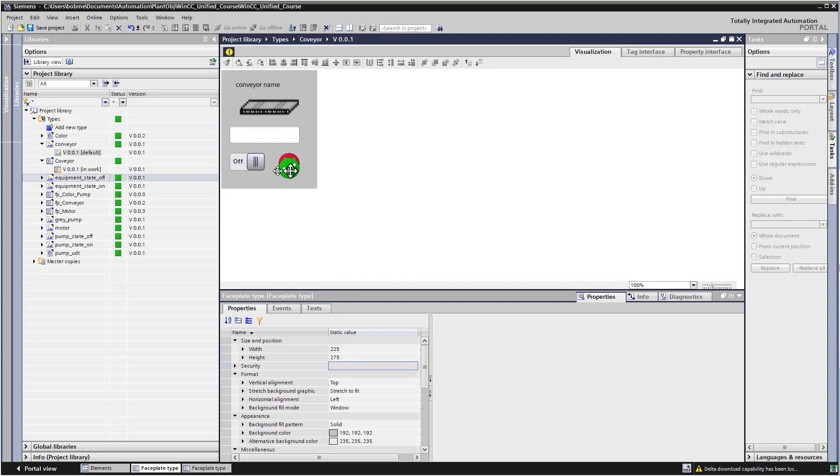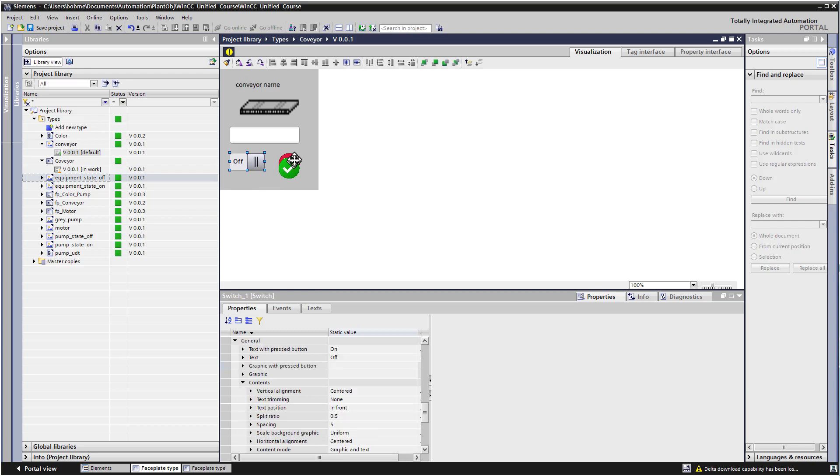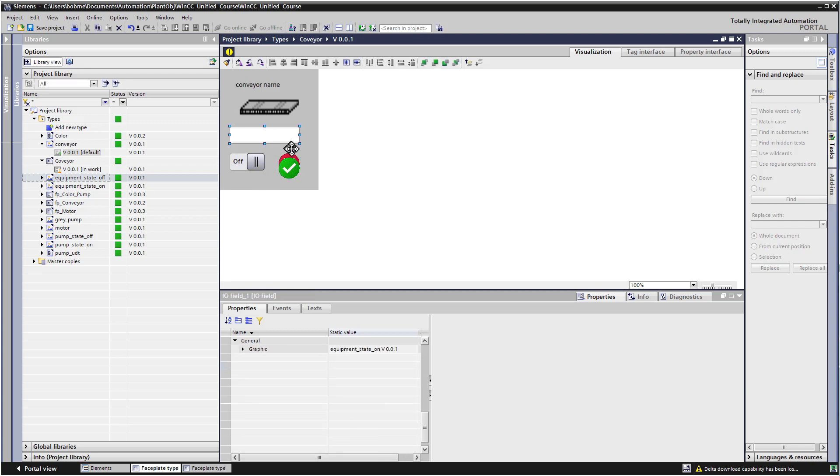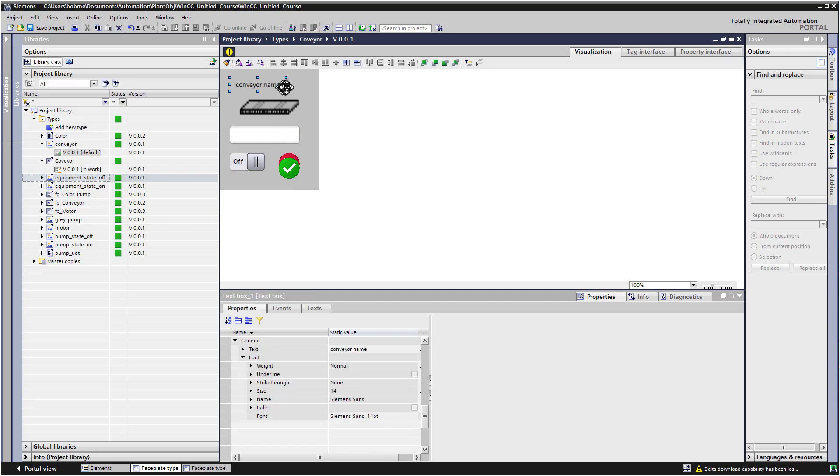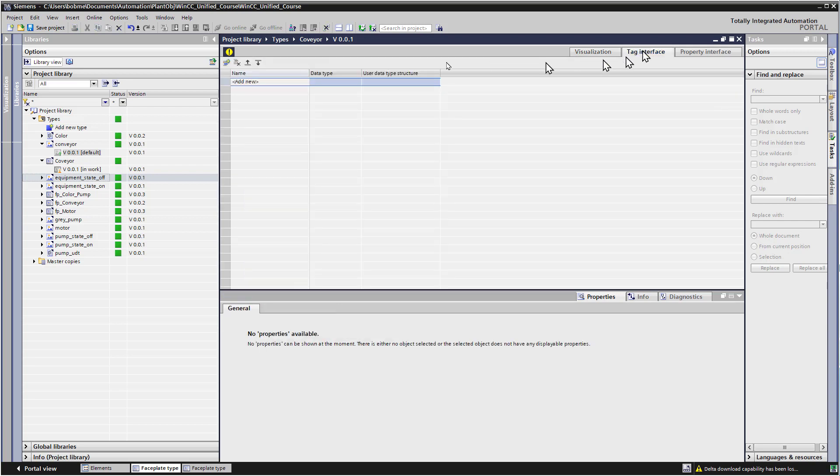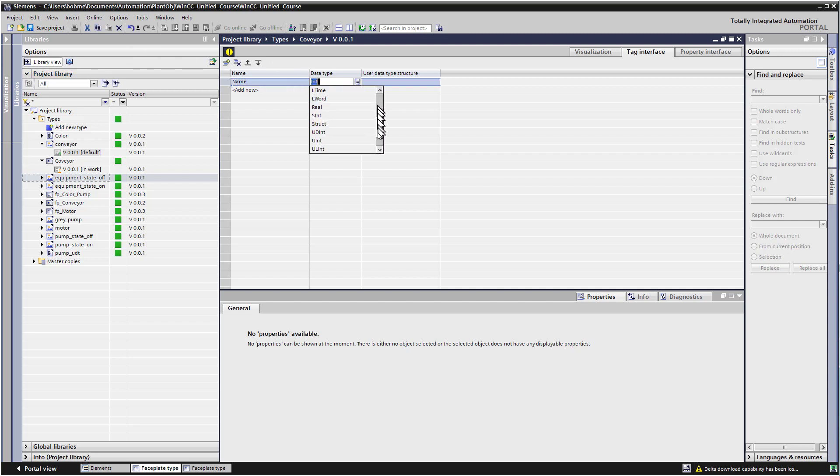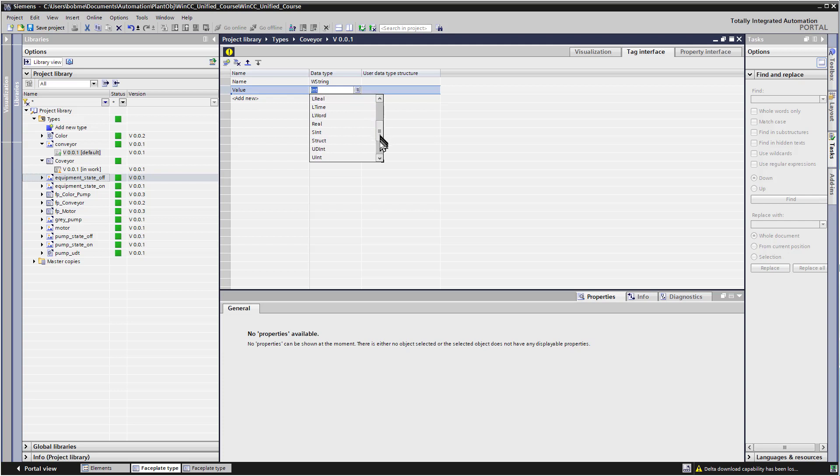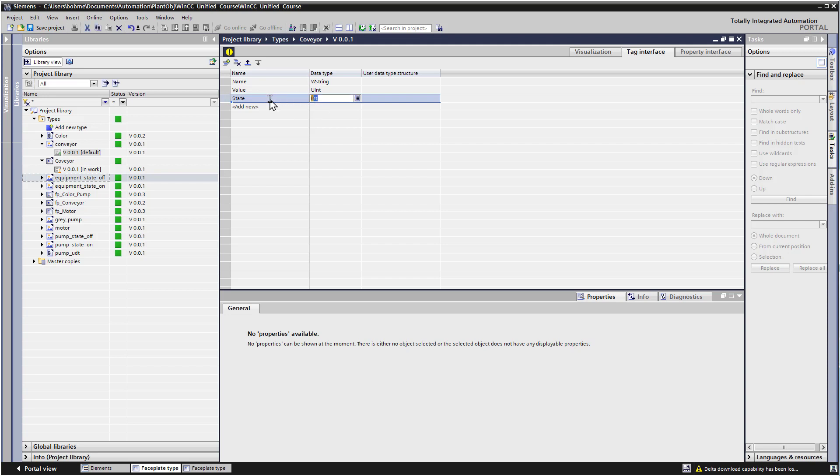And we need some properties. We need a state property which will allow us to hide or show this graphic. We're going to need a value property that we can assign to the IO field. And then we need a name property that we can assign to this. So we'll go to our tag interface, and we're just going to create the same properties here. So there's name, and there's my W string, and then value. And we did an unsigned int on that. And then there's our state, of course, and I can just start typing and do boolean here.